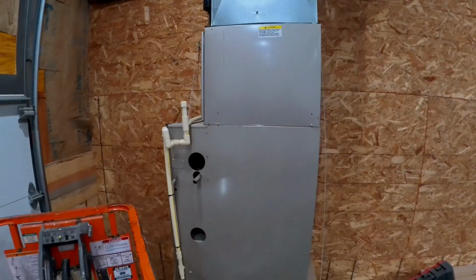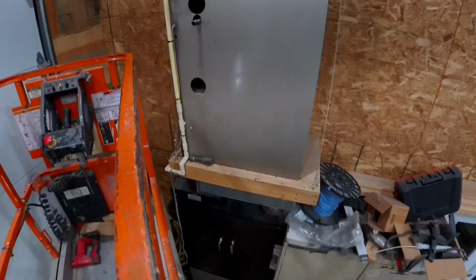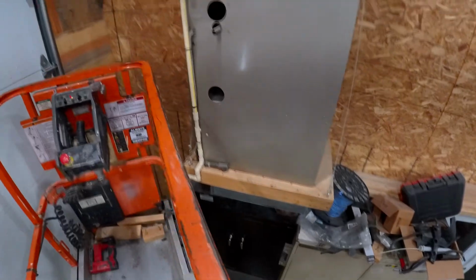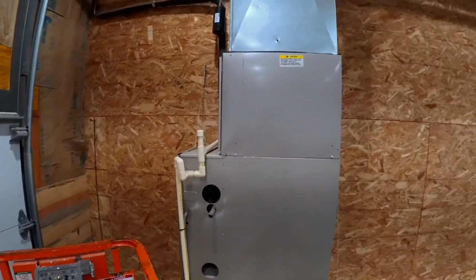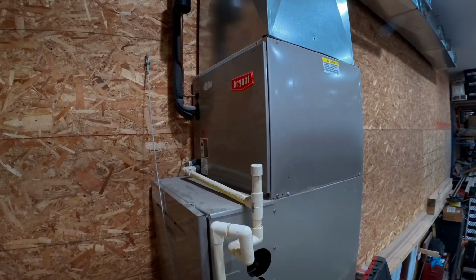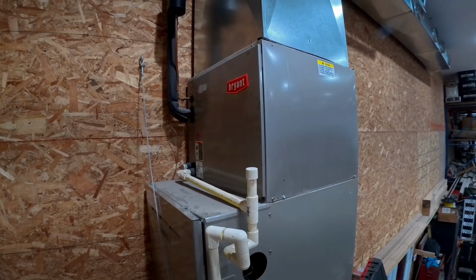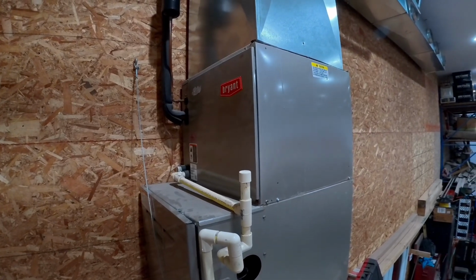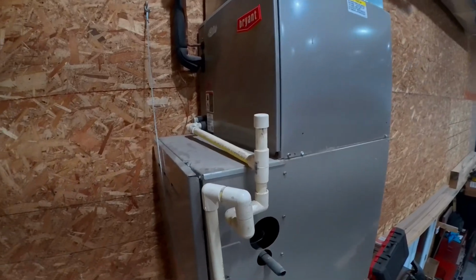The third sign that the system's not running well is condensation on the floor, whether it be from the condensate drain or from the A-coil itself. So if there's water on the floor, it could be from the A-coil freezing up, again from poor airflow, or B, most common, is a plugged condensate drain.